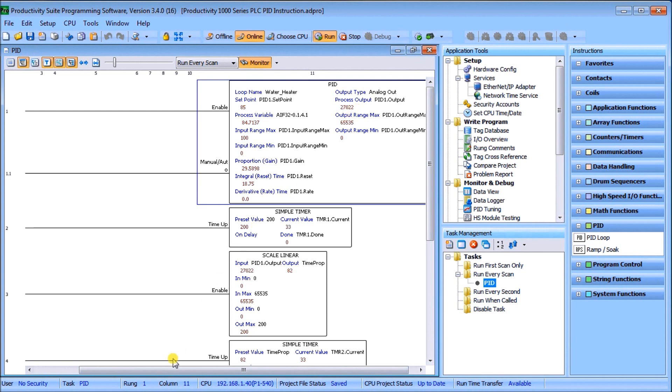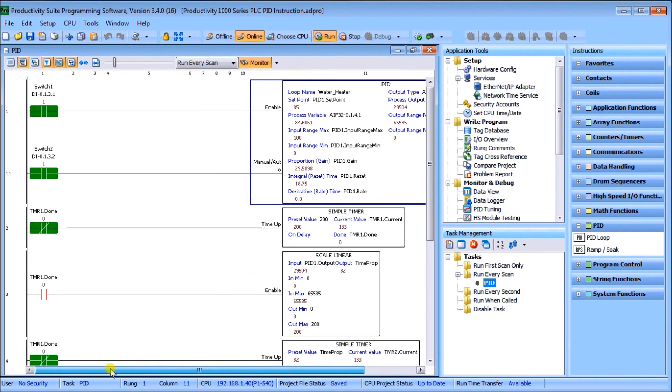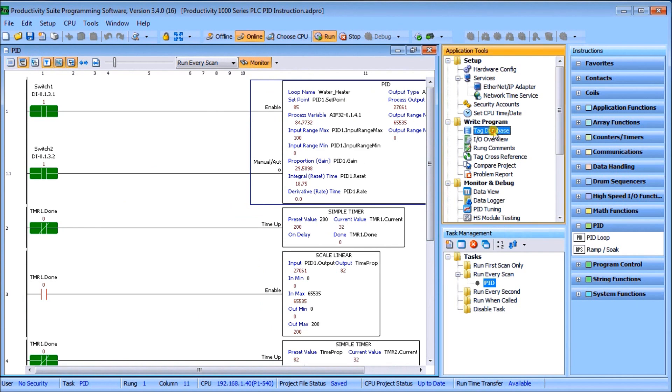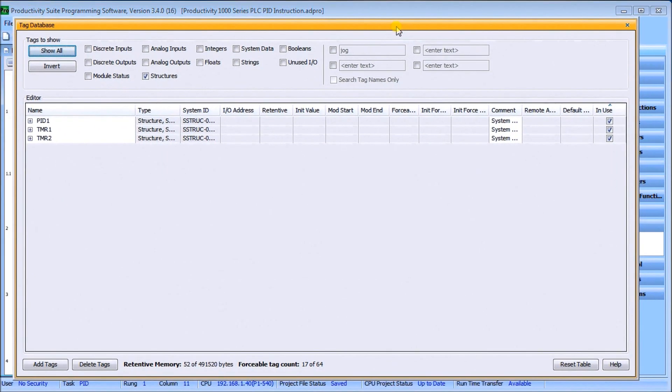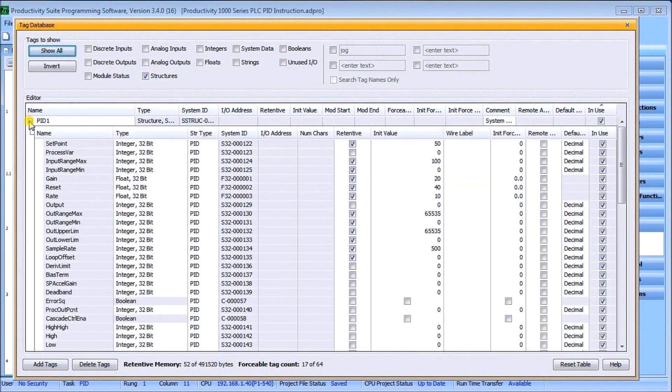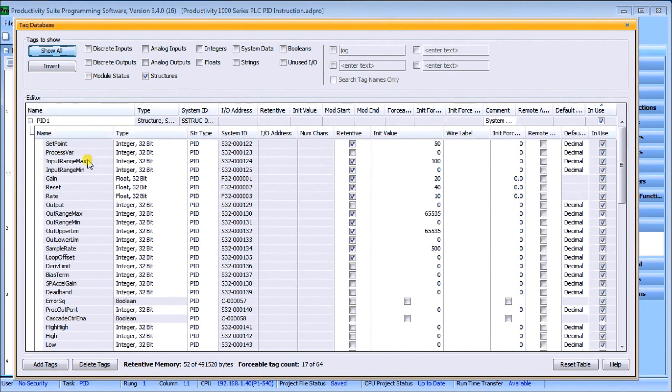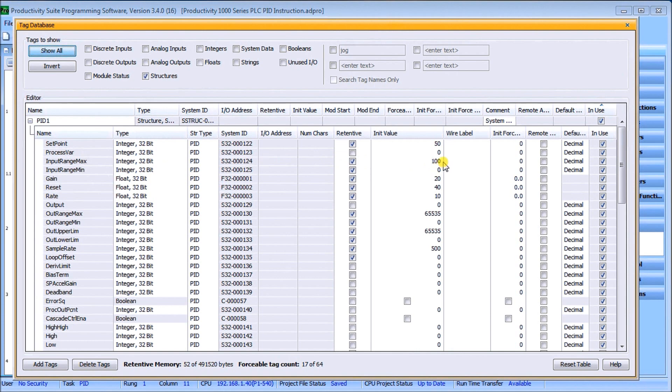If we look at the database, once we have our PID instruction made, look at our tag database. Under our PID loop, our setpoint, we need that and we need our process variable, and we need our input range max and input range min. Now these min and max are going to be set to zero to 100, representing my zero Celsius to 100 Celsius.